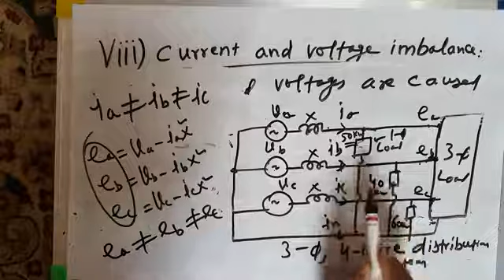This may be 49 kilowatts. So the unbalance is negligibly small. But there is a certain type of single phase loads which cause unbalance. Let us suppose this phase B supplies an electric arc furnace, which is also a single phase load. Electric arc furnace is a large load, a huge load, so that draws a large current.